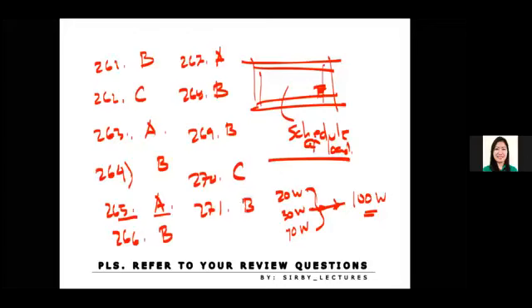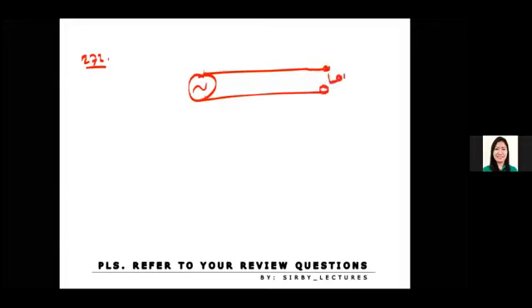Now moving on to our next topic, items 272 to 273, which regard the voltage drop across the line. Number 272. A pole in a farmstead has a source voltage of 230 volts and a source current of 8 amperes. The conductor used is a number 14 wire with a length of 200 feet. Calculate the total voltage drop of the two lines if the resistance is 2.58 ohms per 1000 feet. So the idea is that we have this source right here, and we have this line, and we have our load side.